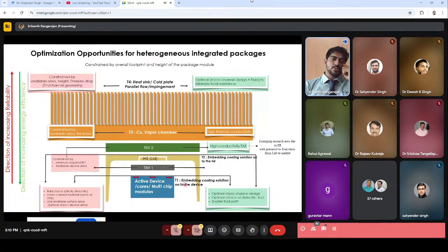With technology 1, the fluid choice has to be strictly dielectric—you can't use liquid water, only dielectric fluids, because you don't want the fluid interacting with active electronic components. Water is known to be the best heat transfer fluid with very high heat capacity, so being restricted from using it means heat transfer performance may come down, and there's also less area available to remove heat. That's a disadvantage of technology 1.